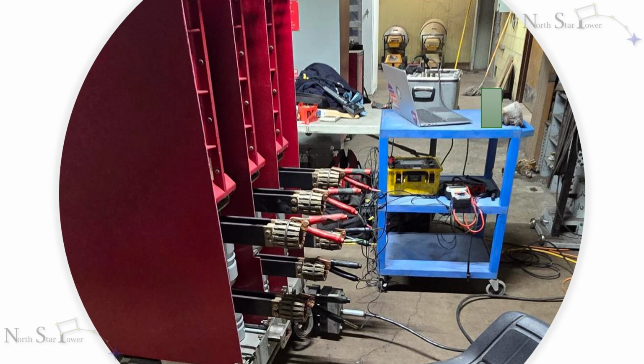We also test the close and trip coils to ensure they still function at a reduced voltage, like during brownouts or battery backup scenarios. According to ANSI and IEEE, coils should still operate at around 70 to 85% their rated voltage. If they don't, the breaker might not respond in an emergency.